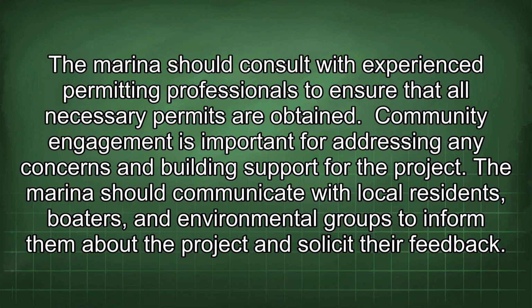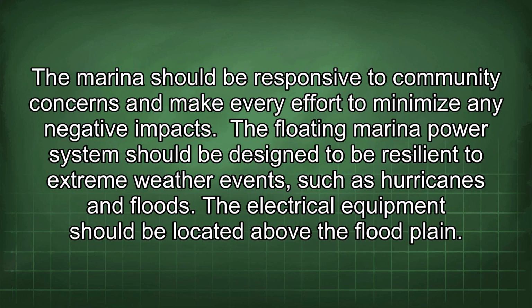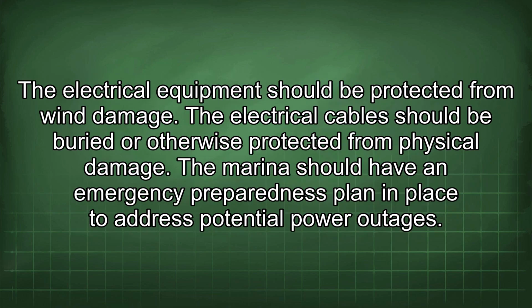Community engagement is important for addressing any concerns and building support for the project. The marina should communicate with local residents, boaters, and environmental groups to inform them about the project and solicit their feedback. The marina should be responsive to community concerns and make every effort to minimize any negative impacts. The floating marina power system should be designed to be resilient to extreme weather events, such as hurricanes and floods. The electrical equipment should be located above the floodplain. The electrical equipment should be protected from wind damage. The electrical cable should be buried or otherwise protected from physical damage. The marina should have an emergency preparedness plan in place to address potential power outages.